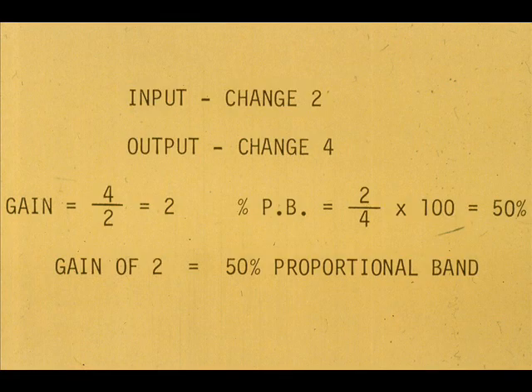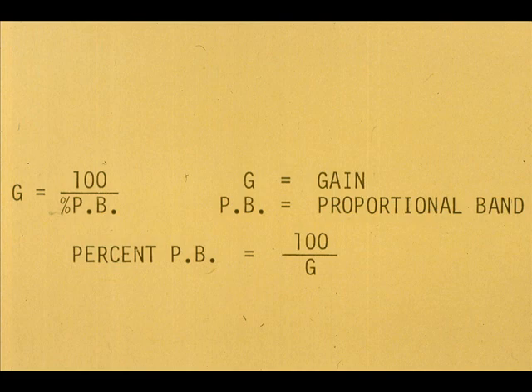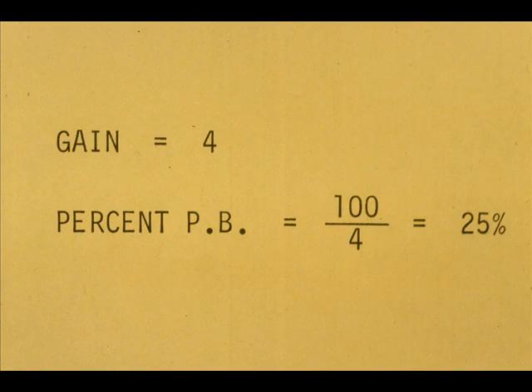We have shown that a gain of two and 50% proportional band are the same. These formulas will convert proportional band. A controller has a gain of four. What is the percent proportional band? From the formula, percent proportional band equals 100 divided by the gain. The answer is 25%.